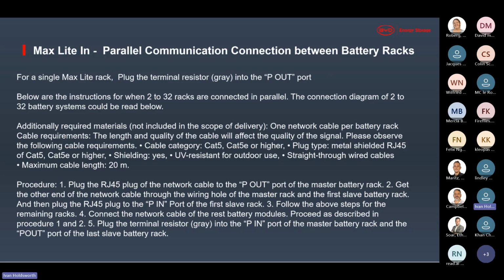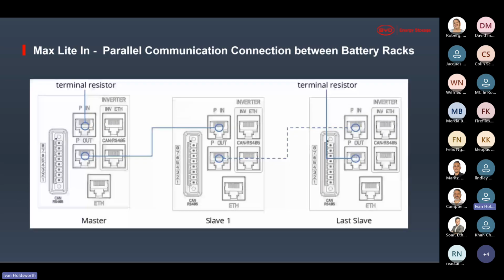For the parallel communications, if you've got only a single tower, it's important to have the termination resistor in the P out port. And if you've got multiple towers, it's important to have the communications cables as shown, with the termination resistor in the P in of the master tower and the P out in the slave tower.